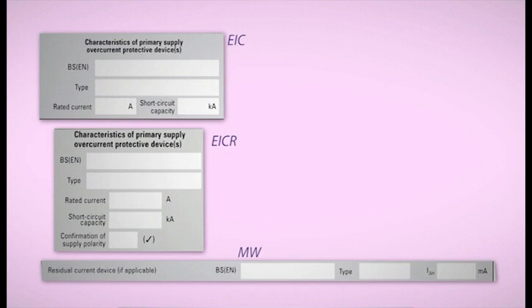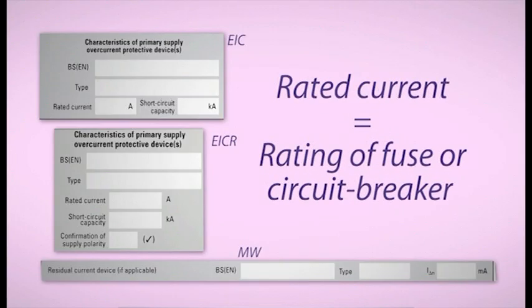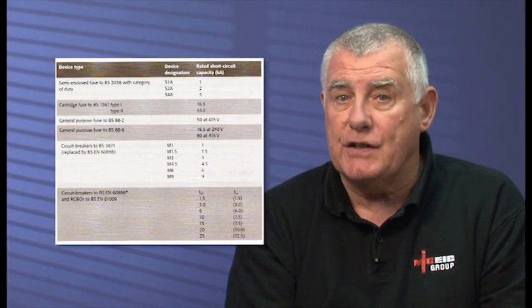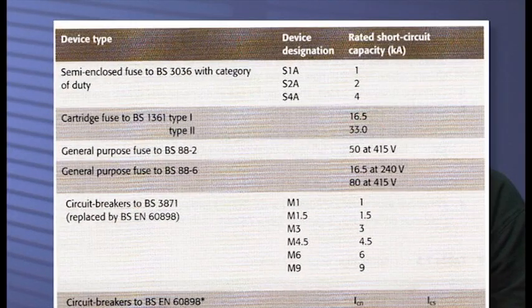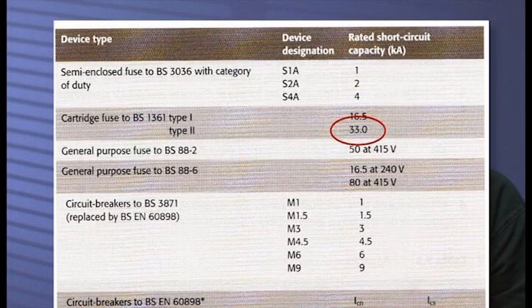The next 2 boxes are rated current and short circuit capacity. The rated current is fairly straightforward, as it's the rating of the fuse or circuit breaker. Short circuit capacity, on the other hand, is the maximum fault current the device can interrupt safely. Looking back at the data, we can see that a BS 1361 Type 2 fuse has a rated short circuit capacity of 33 kA. And it's this value which must be higher than the prospective fault current we spoke about earlier. There's a good point of warning here. On a periodic, if you did encounter a 3036 rewirable fuse as the primary supply overcurrent device, this could have a rated short circuit capacity as low as 1000 amps, depending on its designation.